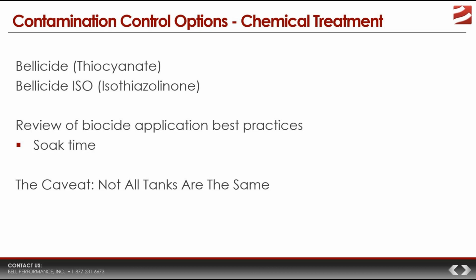Sometimes there are tanks that may require two or even three applications. Three is relatively rare, but sometimes you may need to do a second application. How would you know when you need to do this? Only if you're utilizing something like field portable ATP testing within the context of a good condition monitoring program. Only by doing that kind of testing can you determine if the microbe levels after treatment have actually been reduced to your desired level.